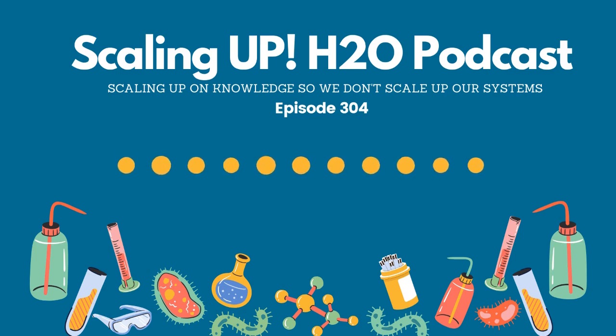And if it's a regular HVAC cooling tower or a process cooling tower, chiller or closed loop system, something like that, the Association of Water Technologies has a standard guideline that they have put into the marketplace to say this is what is acceptable for mild steel and copper. And I will make sure to have that on my show notes page so you can see exactly what that is. But I do want to explain a little bit about how the analysis works.